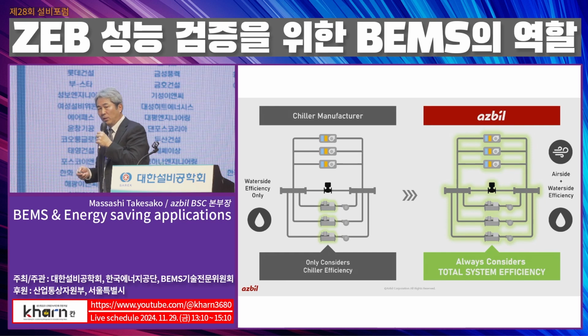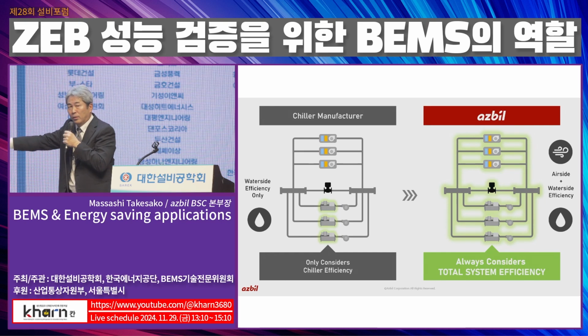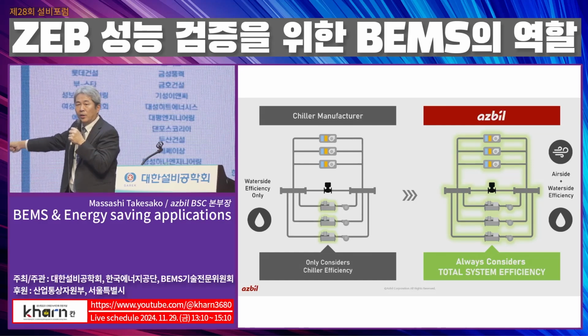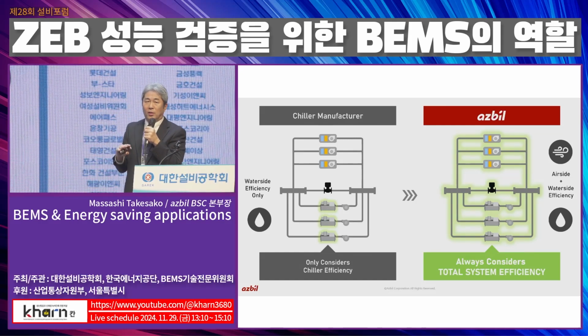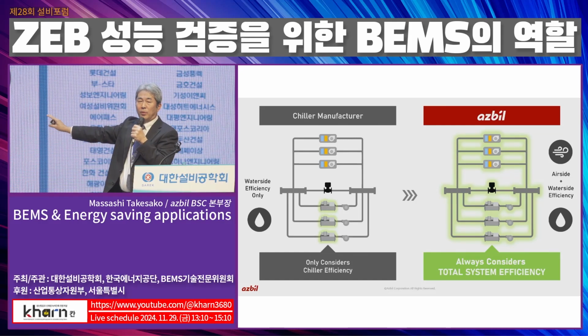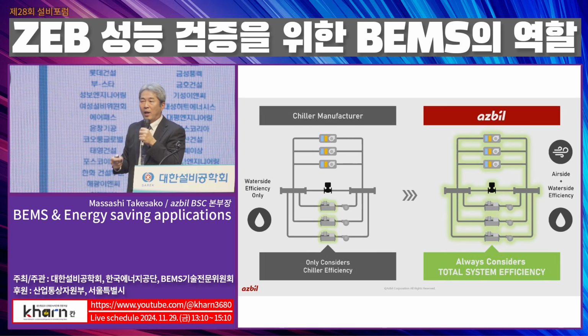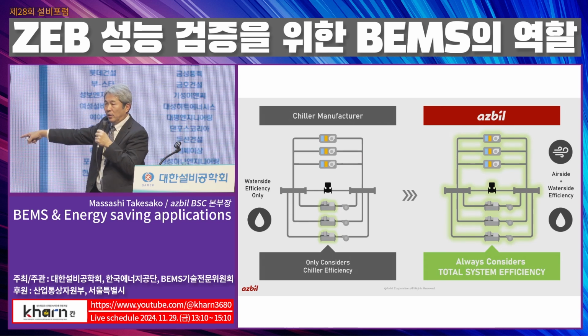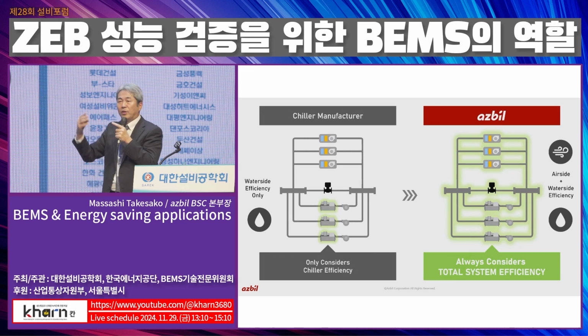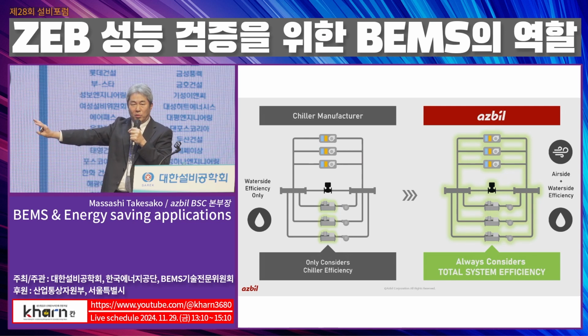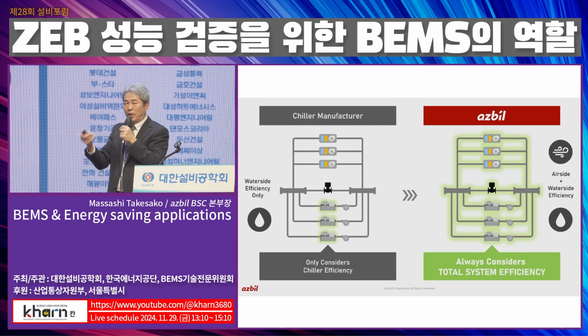So our target is to improve the entire chiller plant efficiency. Not only the chiller itself, not only the pump, not only the fan. The entire chiller plant efficiency has to be improved, because the entire chiller plant consists of various facilities, not only the chiller itself, but also the primary pump, condenser pump, cooling tower fan, sometimes the secondary pump also. Considering all those facilities, we have to find the best operating point.